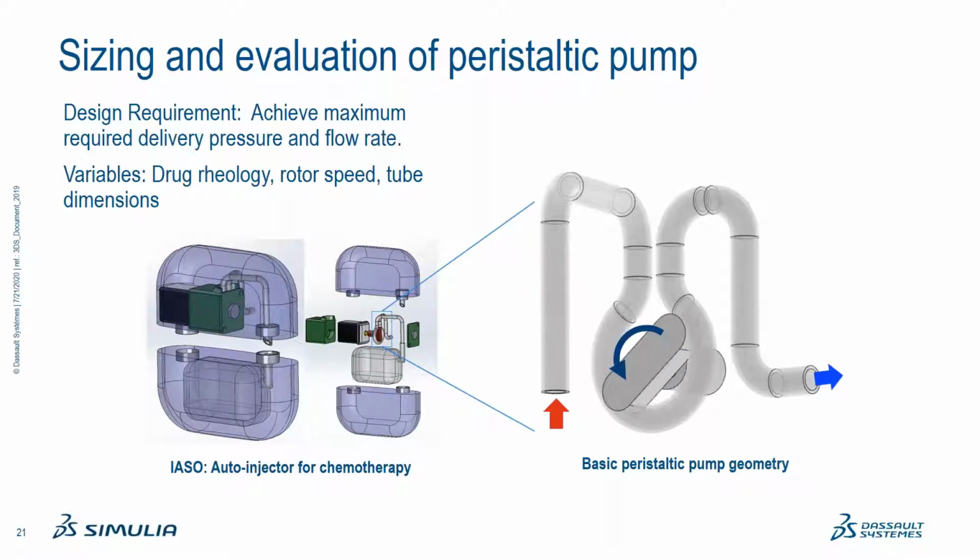Moving on, in this illustration, a device engineering team must engineer its own pump for a wearable drug injector, the best choice being a peristaltic pump. The performance of the pump is dependent upon a number of parameters, including the diameter of the main flow tube connecting the drug reservoir to the cannula in the skin, the pinch load of the rotor on the tube, and the speed of rotation of the rotor.